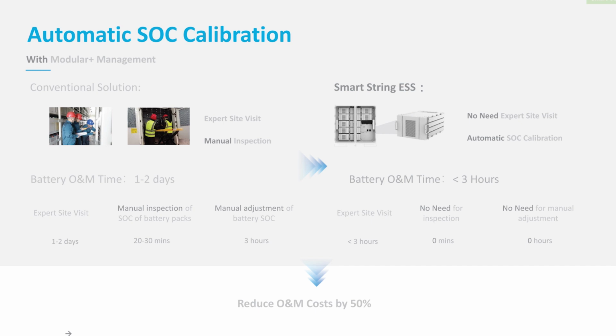Automatic calibration. Our battery does automatic SOC calibration on a daily basis. We make sure that each battery is fully charged to 100%. Once it's charged to 100%, it's bypassed so the other batteries can charge, and you don't overcharge from one battery to another. Normal SOC calibration for a competitor would mean you need to go to site, stop the system, connect up to each battery and do the calibration. So on a 100 megawatt hour plant, it's 300 man days. On a 10 megawatt hour plant, you're looking at 3 days.